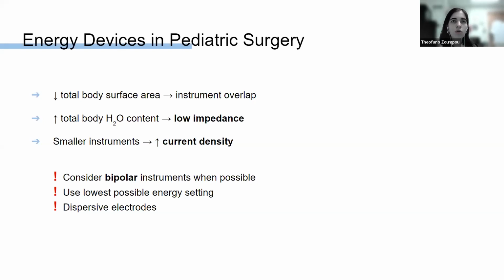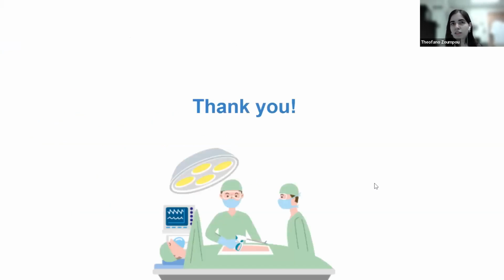Three general rules that are good to follow are: one, we should consider using bipolar devices, not monopolar devices, when we have this choice. Two, we should always use the lowest possible energy setting that can give us the desired effect. And that goes for adults as well. And number three, we should keep in mind that there are special considerations regarding the use of dispersive electrodes in infants and children. And that brings us to the end of this presentation.